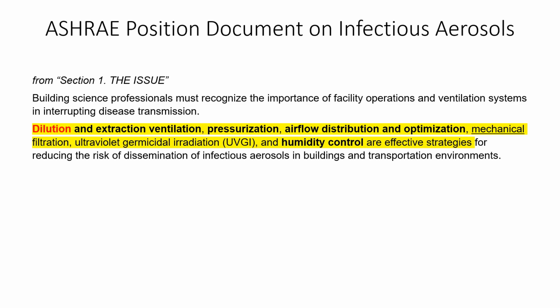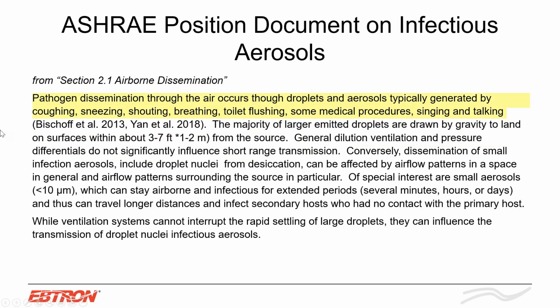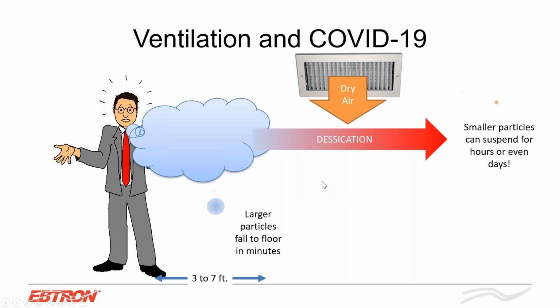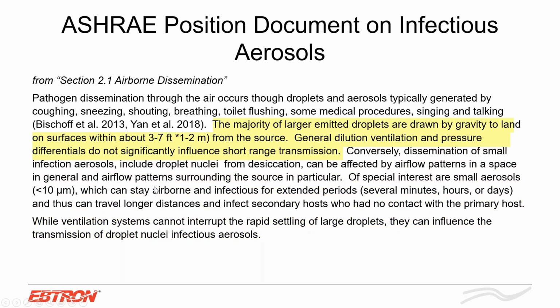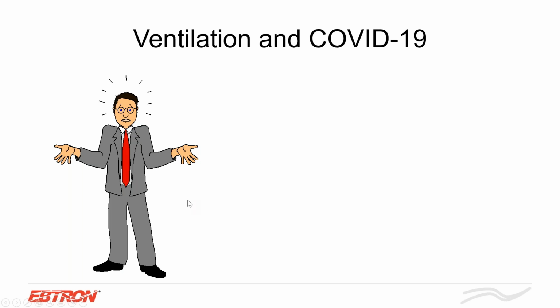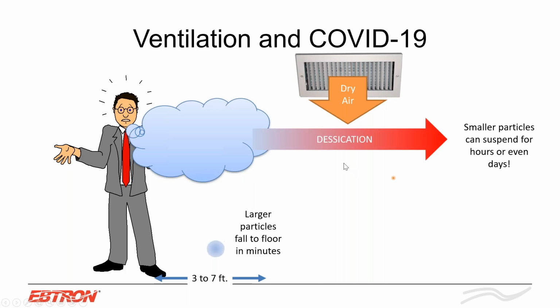What does that mean? That means we can help by providing dilution ventilation for reducing the risk of infectious aerosols such as COVID-19. They go further into talking about it, and they say that pathogen dissemination does occur through the air. And they say, while ventilation systems cannot interrupt the rapid settling of large droplets, they really can influence the transmission of droplet nuclei. So what does this mean for us? Well, typically, when we breathe out, larger particles normally fall to the floor within a few minutes. And if you'll notice here, ASHRAE said droplets travel about 3 to 7 feet from the source. And that's why during COVID there was that maintained 6-foot distance, right? But also you have desiccation occurring, and smaller particles can stay suspended in the air for hours or even days. So that's where dilution ventilation really comes into play.